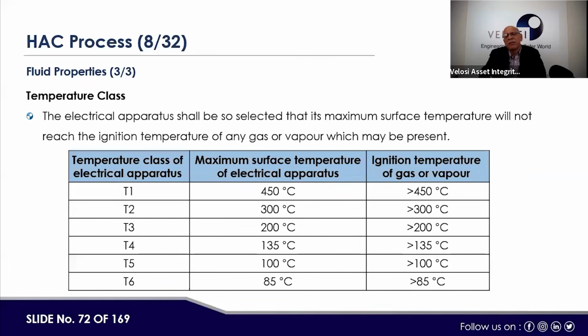Then temperature class: this is the class applicable when we select an instrument or equipment, so that the surface should not create a temperature more than the temperature for that temperature class. For example, T6 means the surface temperature of that particular equipment should not cross 85 degrees Celsius, right? T5 is 100, T4 is 135, and T1 is 450 degrees Celsius. The ignition temperature of a gas or vapor in this case would be above 450, because the hydrocarbon which may be released in that equipment is also given, along with the maximum temperature allowed. So the auto-ignition temperature of that fluid should be greater than the temperature of any hot surface which could be in that hazard classification area.